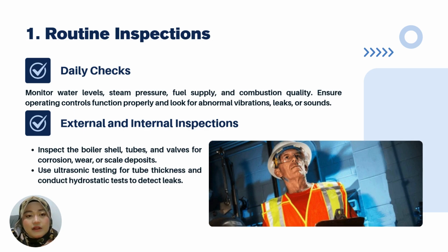First, we have routine inspections. Routine inspections involve daily checks and also external and internal inspections. Daily checks include monitoring water levels, steam pressure, fuel supply, and combustion quality. Ensure operating controls function properly and look for abnormal vibrations, leaks, or sounds. External and internal inspections involve inspecting the boiler shells, tubes, and valves for corrosion, wear, or scale deposits. Use ultrasonic testing for tube thickness and conduct hydrostatic tests to detect leaks.